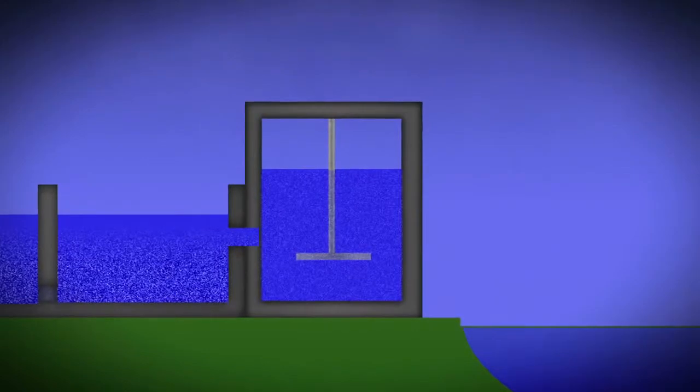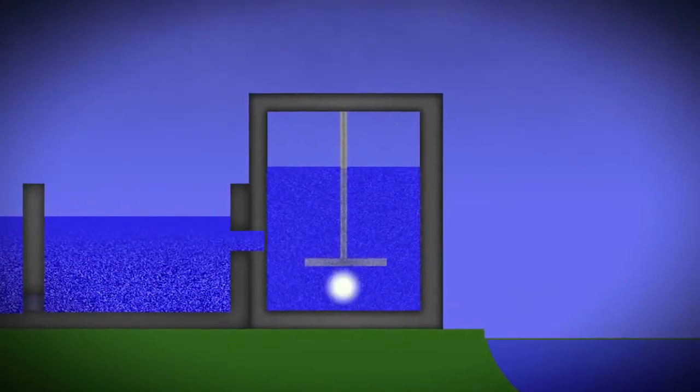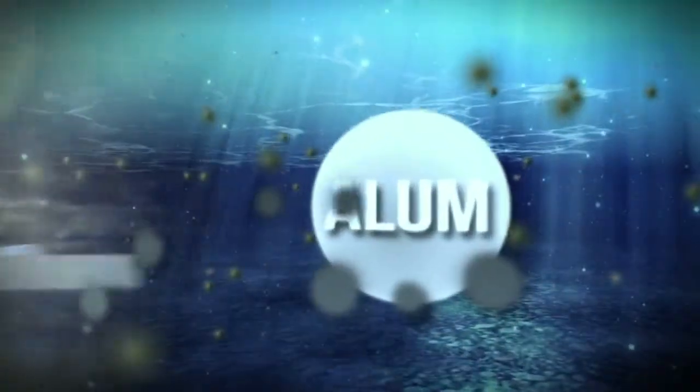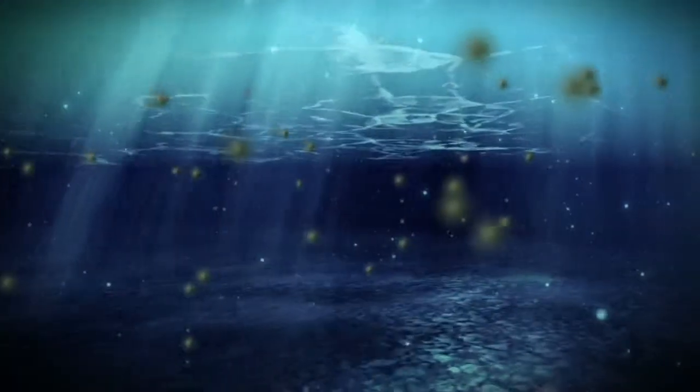To start the treatment process, water is pumped up into a rapid mix tank where alum and lime are introduced into the water. The lime adjusts the pH, and the alum begins the process of attracting foreign particles too small to be filtered. The particles clump together with the alum, forming larger particles that eventually sink to the bottom or can be filtered out.